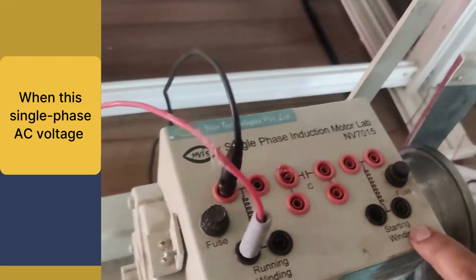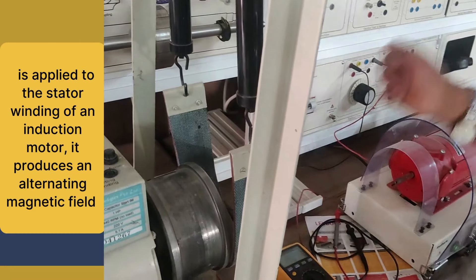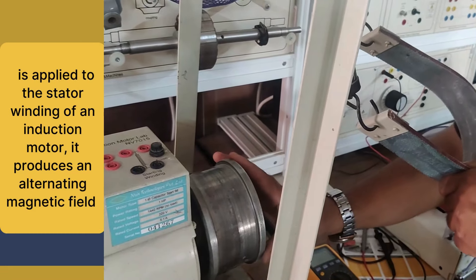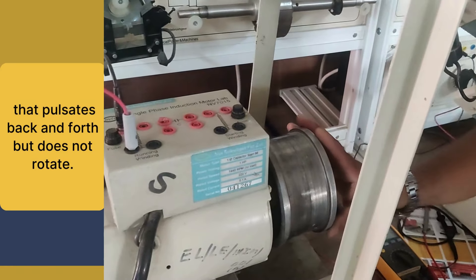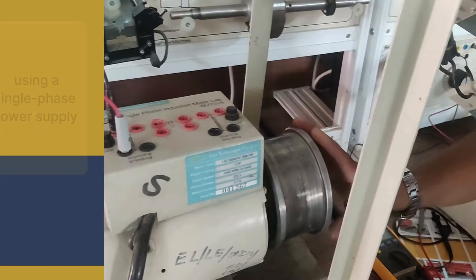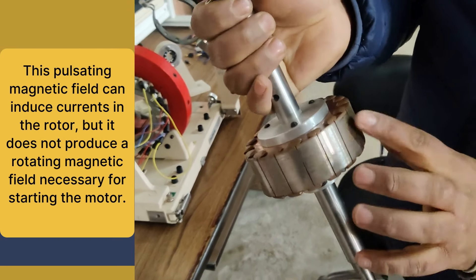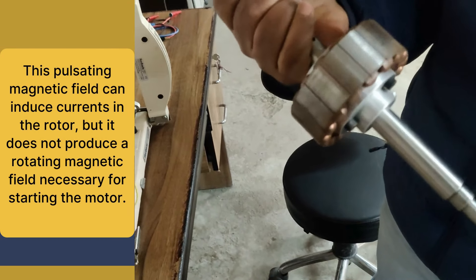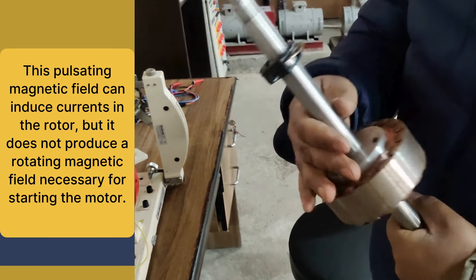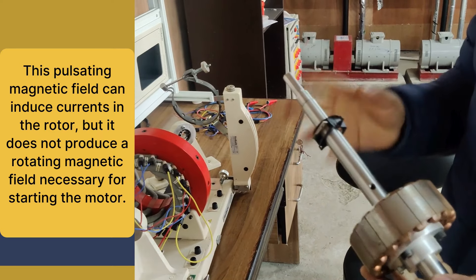A single-phase AC supply provides a single-phase sinusoidal voltage that oscillates over time. When this single-phase AC voltage is applied to the stator winding of an induction motor, it produces an alternating magnetic field that pulsates back and forth but does not rotate. This pulsating magnetic field can induce currents in the rotor, but it does not produce a rotating magnetic field necessary for starting the motor.